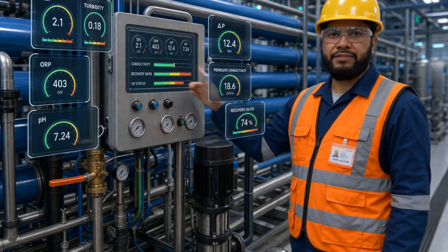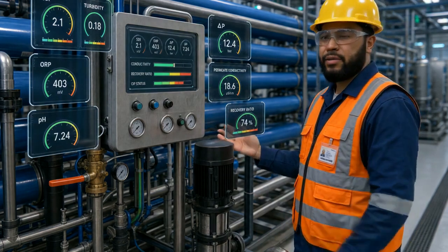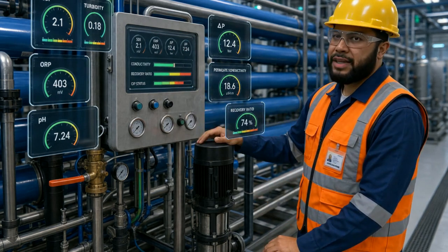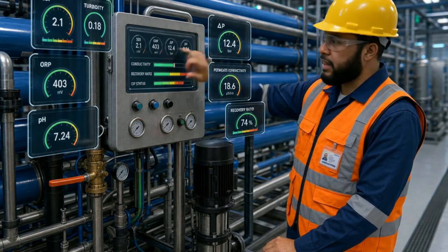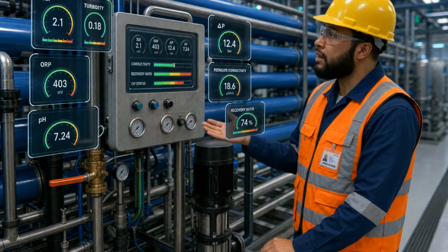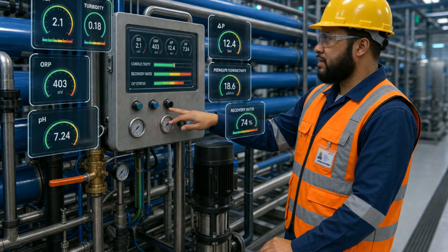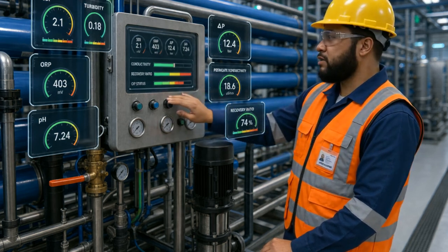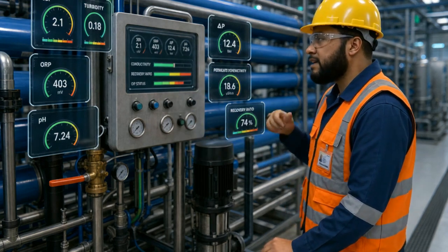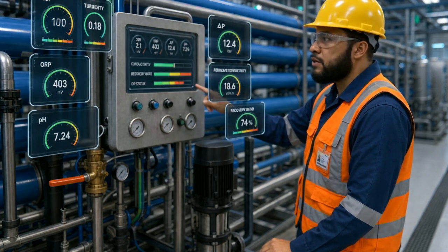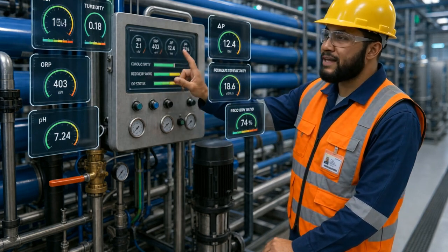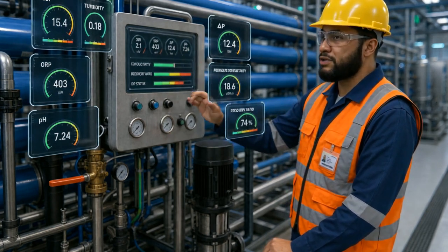To keep an RO plant efficient and prevent premature membrane failure, operators should continuously monitor the condition of both the feed water and the membrane train. First, watch silt density index and turbidity. As a practical target, SDI should remain below 3 to reduce particulate fouling risk. If SDI begins rising, the problem is usually upstream in clarification, media filtration, cartridge filters, or chemical dosing. Second, monitor oxidation reduction potential and pH. Free chlorine can permanently damage polyamide membranes, so ORP confirms that dechlorination is effective before the water reaches the RO.